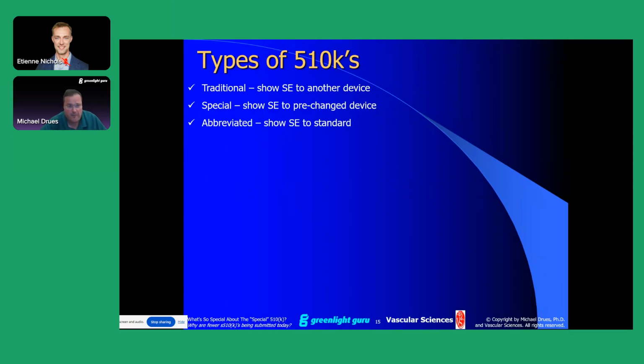And then finally, the third major type of a 510K is what we call the abbreviated 510K. And here we also have to show substantial equivalence, but we do not show substantial equivalence to a particular device. Instead, we show substantial equivalence to a standard, to a guidance document, to an ISO or ASTM standard or something like that. And the logic, very briefly, for the abbreviated 510K is that if we comply to this particular standard and all of these other devices in this product code also comply with that particular standard, then it stands to reason that our device is substantially equivalent to the other devices because they all meet the same standard or standards plural, right? So that's in essence the abbreviated 510K.